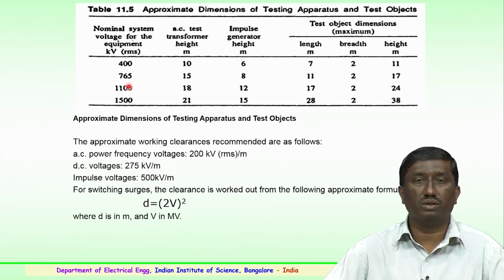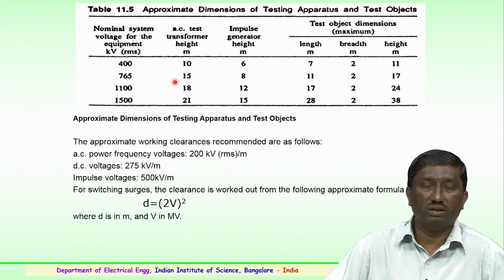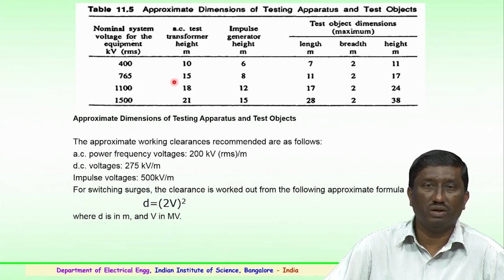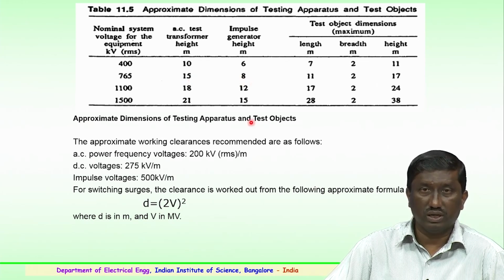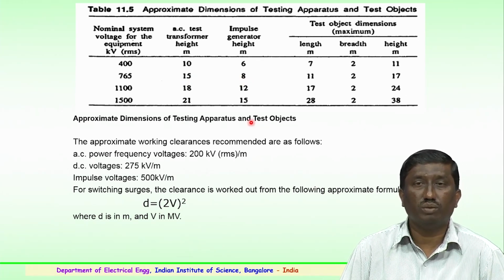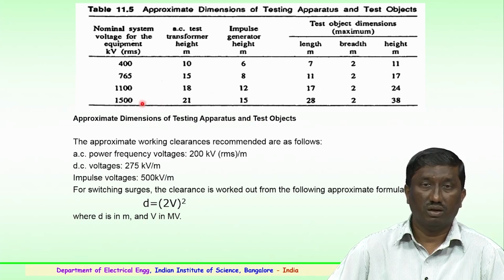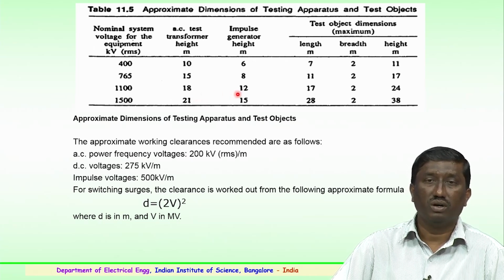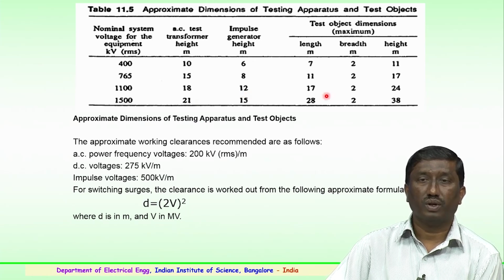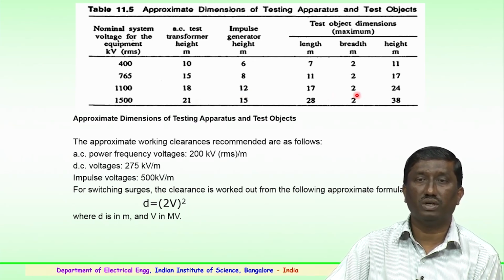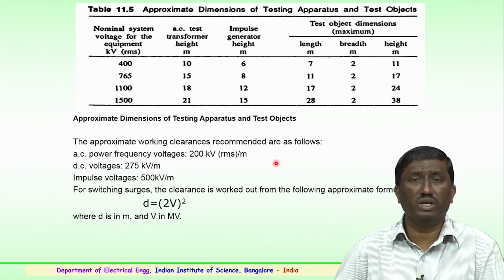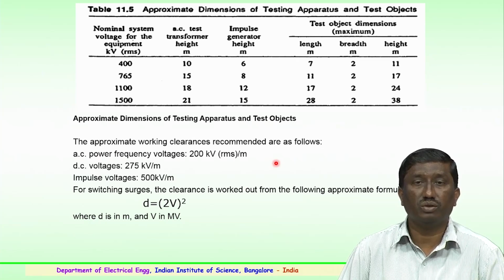Similarly, for a 765 kV system, the AC test transformer height could be around 15 meters, that is around 45 feet. For the impulse generator it could be 8 meters, and the test object dimensions could be 11 meters in length, 2 meters in breadth, and 17 meters in height. As the voltage level goes higher, for 1100 kV the dimensions also change: 18 meters for the transformer height, 12 for the impulse generator, and 17, 2 and 24 for the length, breadth and height of the test objects. These are the approximate dimensions of the testing apparatus and test objects.